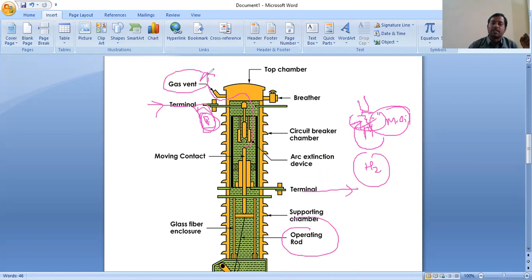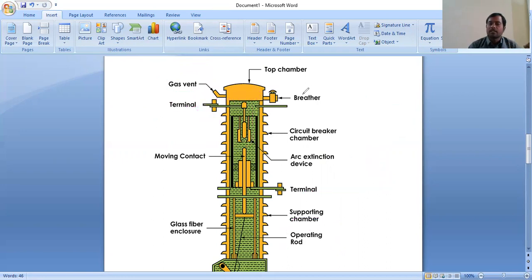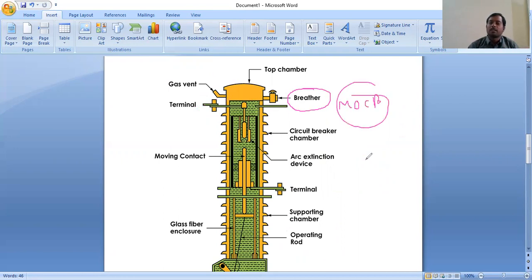That is nothing but a gas vent. This is the top chamber. The top chamber is used to refill the oil again, and whenever compression and expansion of the oil takes place, the top chamber will operate — just like a surge tank. This is the breather. Whenever gas is sent outside, it will absorb the air from the outside. This is the total about the minimum oil circuit breaker and its function.